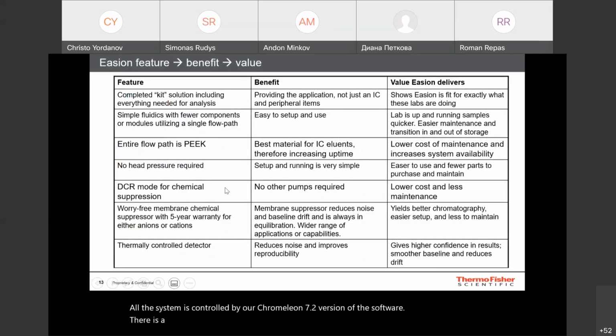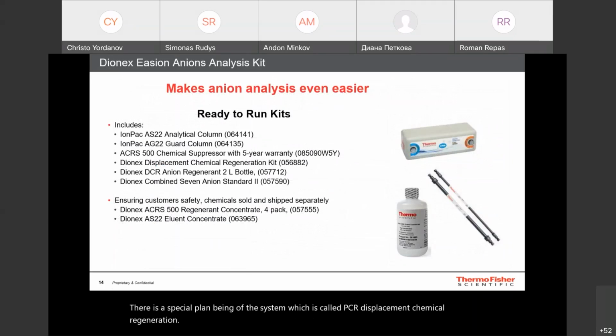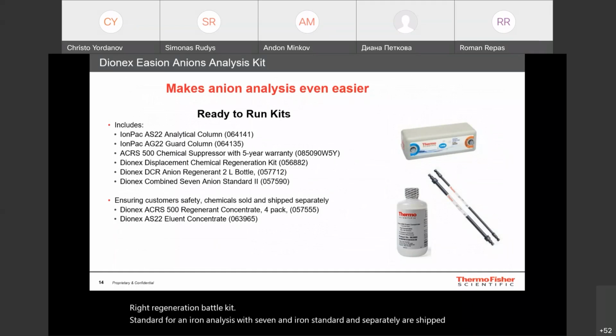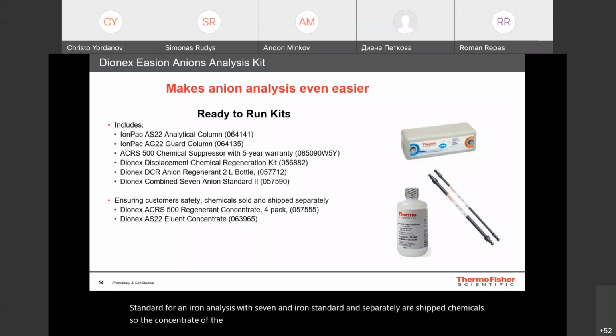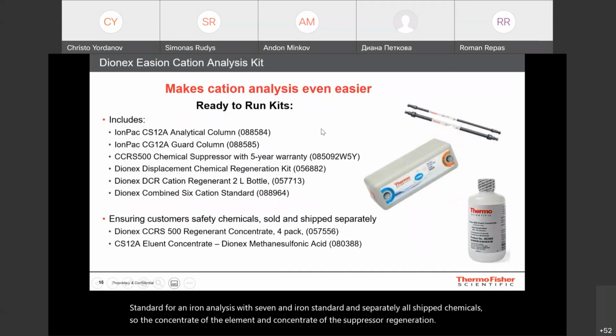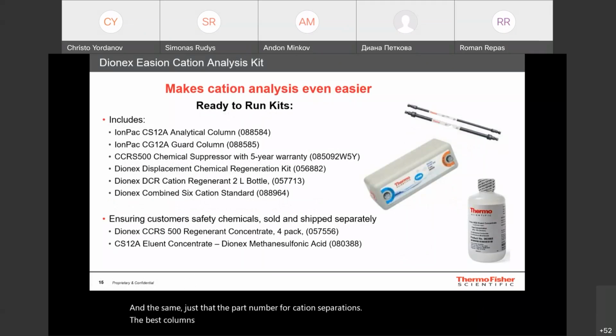There is a special plumbing of the system, which is called DCR, Displacement Chemical Regeneration. And to have the system complete, you need a kit, which includes analytical and guard column, chemical suppressor, regeneration bottle kit, standard for anion analysis, which is 7 anion standard, and separately are shipped chemicals. So the concentrate of the eluent and concentrate of the suppressor regeneration. And the same, just another part number for cation separations. The best columns of choice are CS12A, IonPac CS12A analytical column for the separation of cations, group 1 and 2. And for anions is the column IonPac AS22.